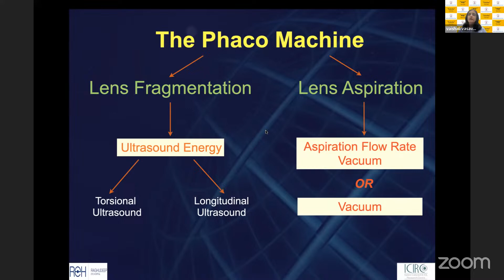Now, the second part, once you have divided the lens, is how you remove the lens. So, lens aspiration, wherein most of us use peristaltic pump machines in which there is an aspiration flow rate and there is a vacuum. But if you are using a Venturi system, then there is only one thing, that is vacuum. There is no separate flow rate and vacuum. So that is also a very important concept to be understood. But except if you are working on a Vitrector machine, which is by default a Venturi system, or on a machine like the Stellaris, which also works on the Venturi principle, most other phaco machines are peristaltic in nature today.